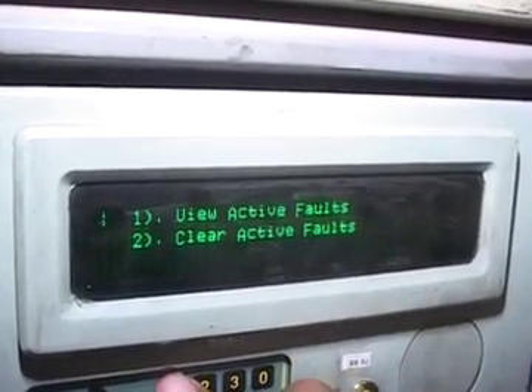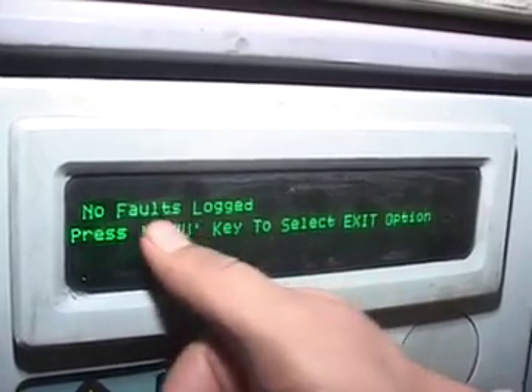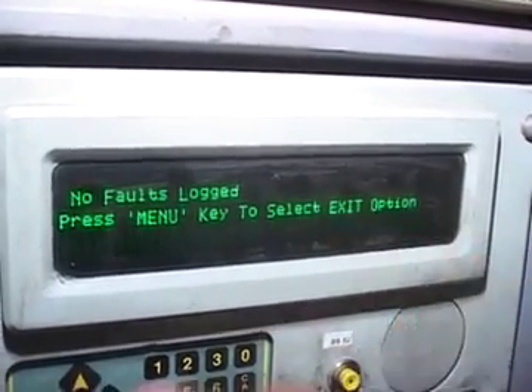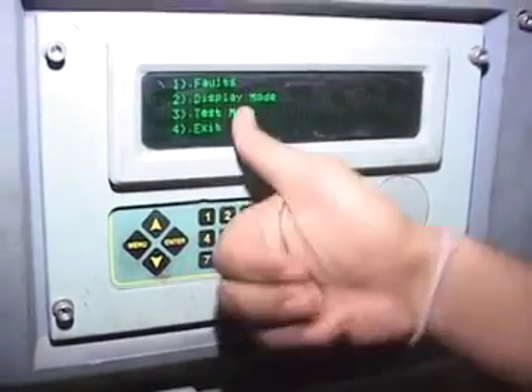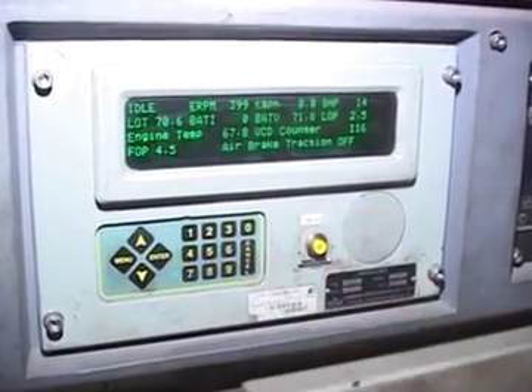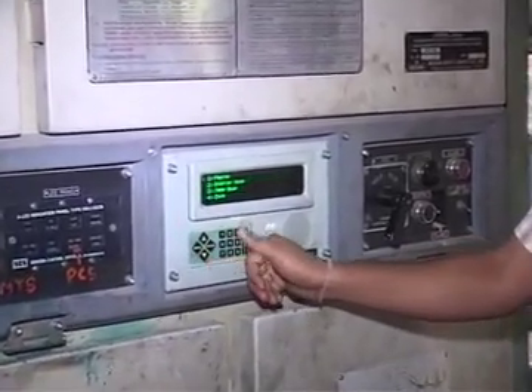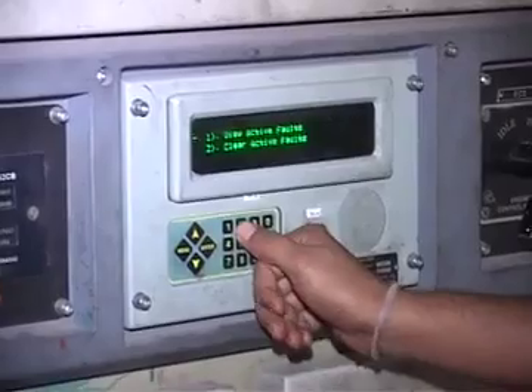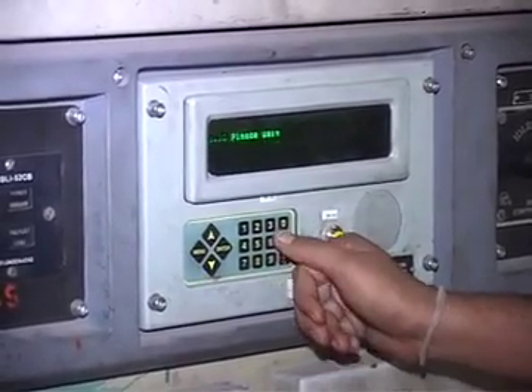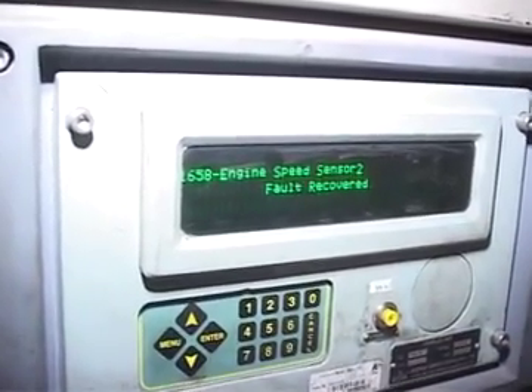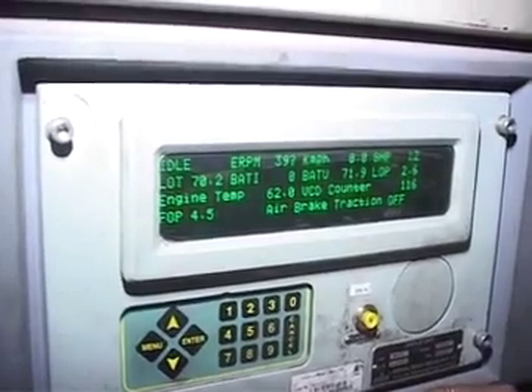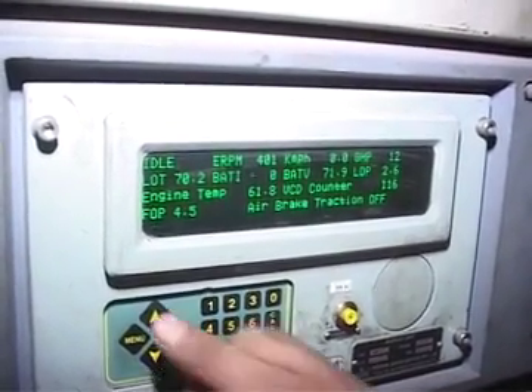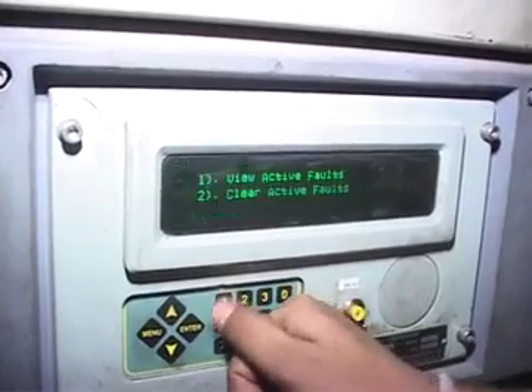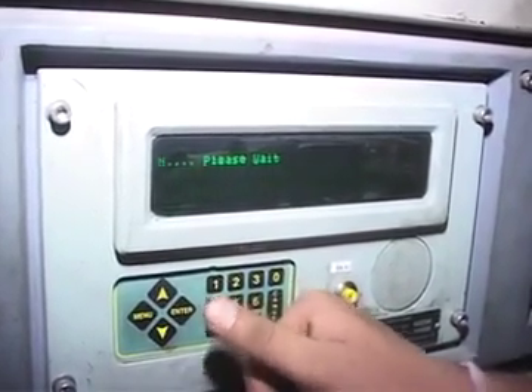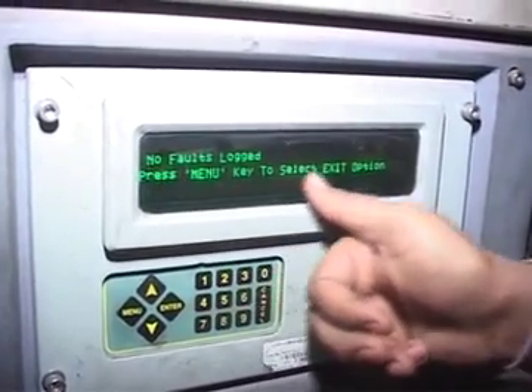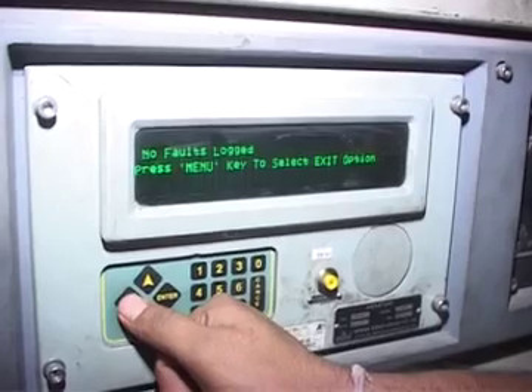View active faults. Registered faults, if any, will be displayed. The user can navigate through the faults using the down arrow key until no more fault log message is displayed. Press the menu key to select the exit option. Clear active faults. Use 0 to clear faults; a message will be displayed. After a few seconds, logged faults are displayed one by one. After noting down the faults, to clear a fault, press the 0 key and the down arrow key to see the next fault. Continue the above till all faults are cleared. Press the menu key to select the exit option.